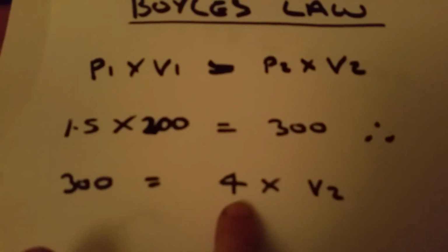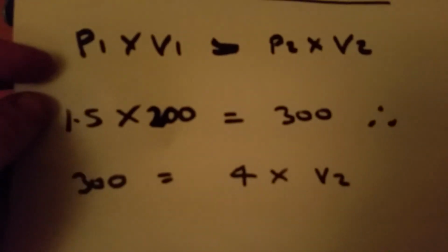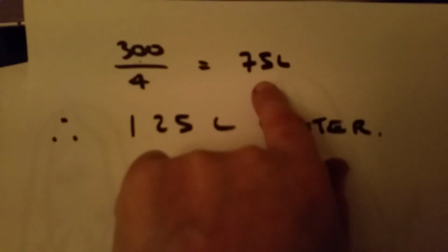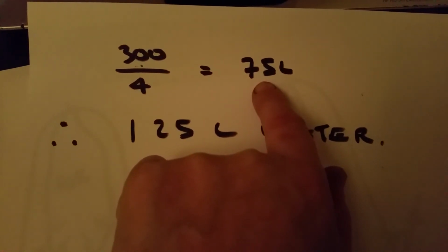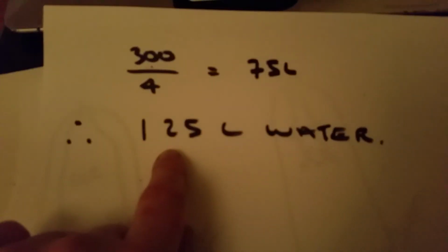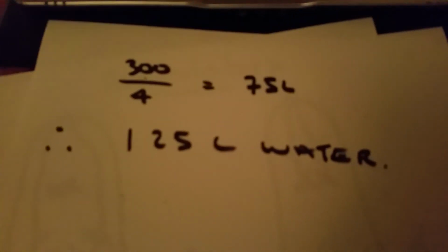Take the value, divide it by your final pressure, either pump pressure if you're filling it with a pump, or the standing pressure in the street, which will give you your new air volume. Take the original volume of the vessel, take off this reduced volume of air, giving you the storage capacity of the accumulator. From there you can work out how many vessels you need.